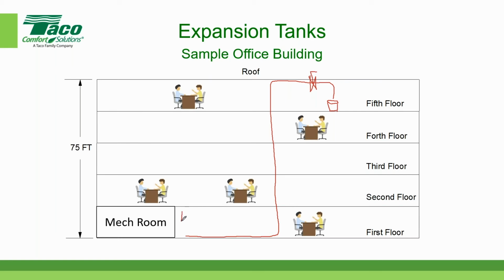And let's say that I have a fill station at the bottom of the building here. And let's say this pipe is capped for right now. And from that fill station, I have a valve. And that valve is a manual valve and allows me to add water to the system. So I'm going to open the valve from my fill station, fill this pipe with water all the way to the top, and then when I get 1 or 2 drops coming out of the end of the pipe, I'm going to close my fill valve down here, and I'm going to close my valve at the top of the building.